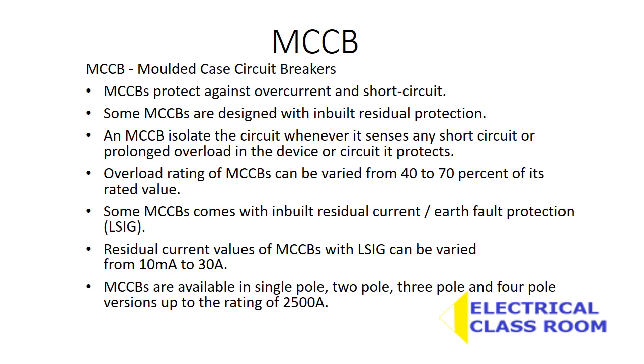The overload rating of molded case circuit breakers can be varied from 40 to 70% of its rated value. Some molded case circuit breakers come with inbuilt residual current and earth fault protection, known as LSIG. Residual current values of MCCBs with LSIG can be varied from 10 milliamps to 30 amps.